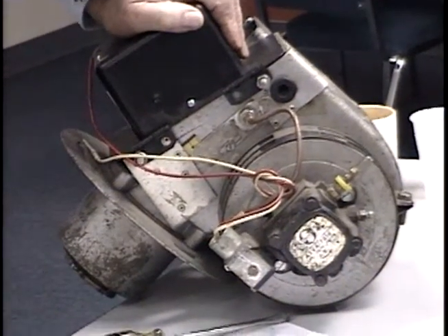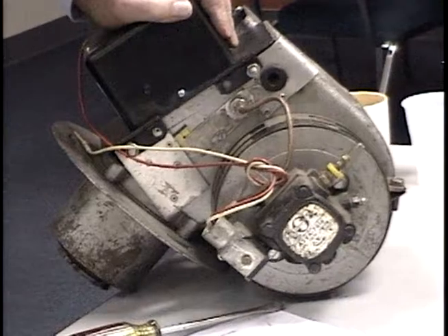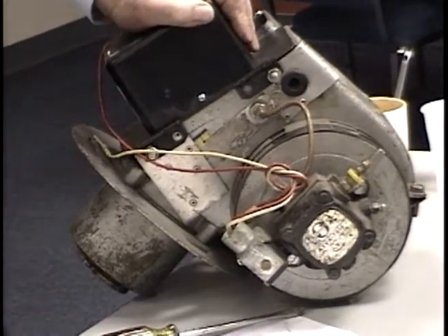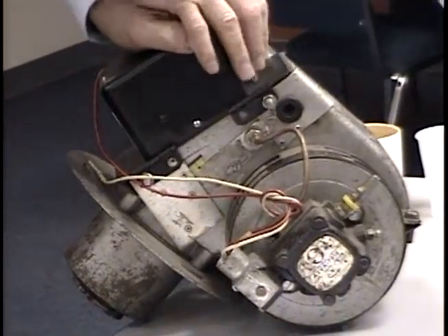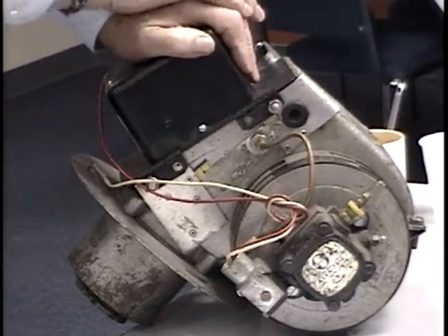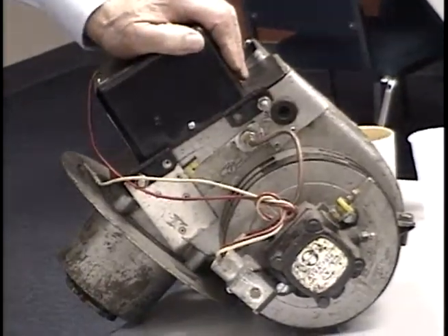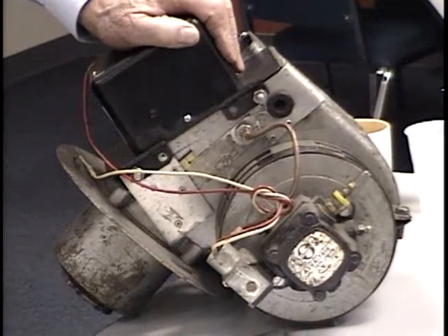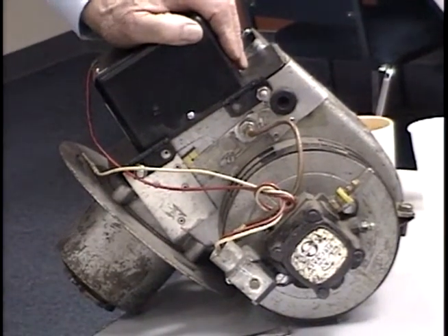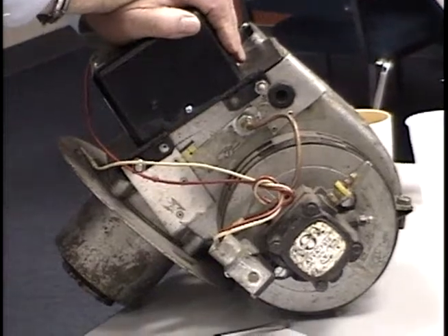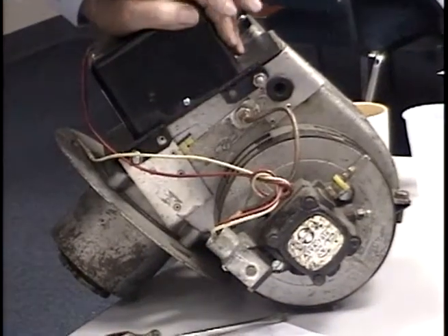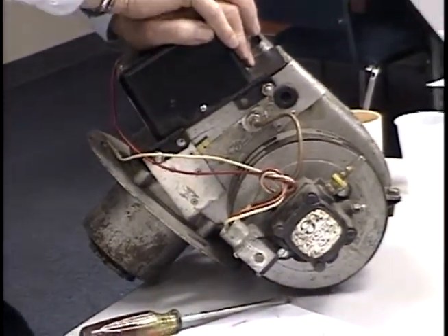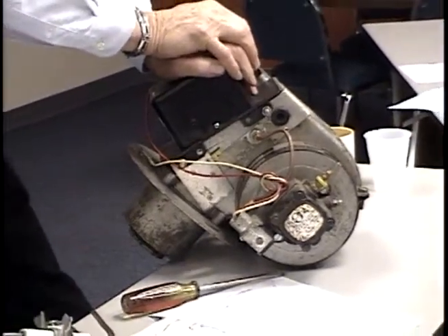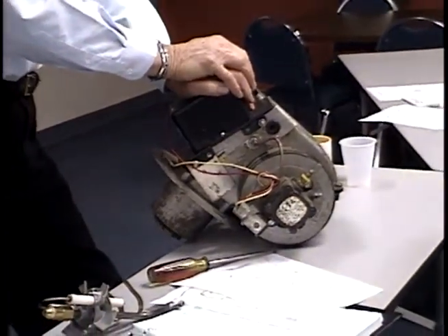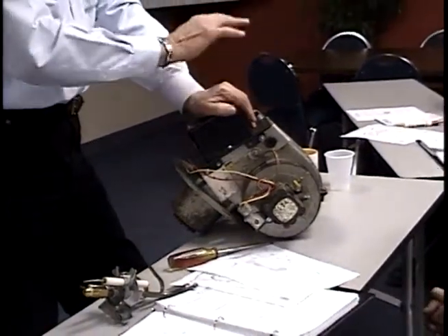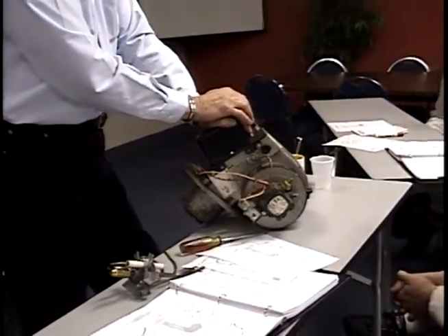Don't expect that this will change at all through many, many years, but down the road somewhere, maintenance and service will be done. Each quarter turn increment on this thing, clockwise, will increase the fuel pressure by 3 to 4 pounds. Counterclockwise will decrease your fuel pressure by 3 to 4 pounds. So if you're jockeying around with it trying to get more heat or save fuel or whatever the situation may be, always keep up with what you've done so you can always go back to square one should you get out of the ballpark someplace.